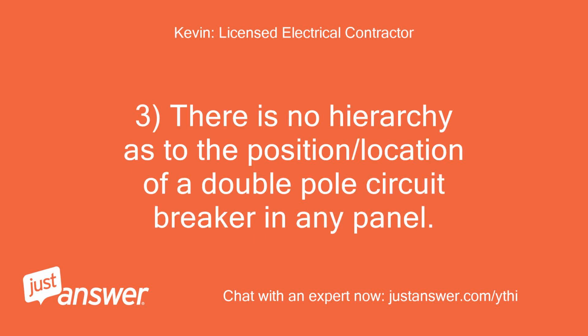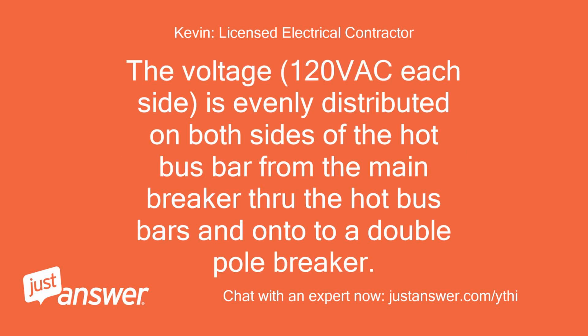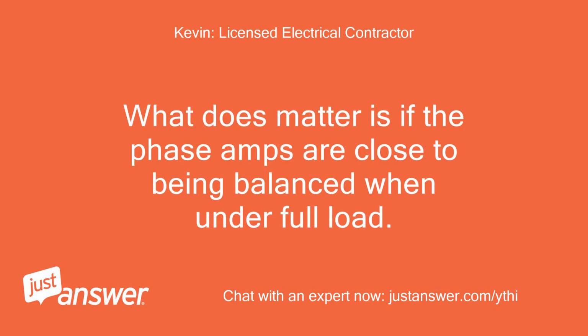3. There is no hierarchy as to the position/location of a double pole circuit breaker in any panel. The voltage, 120 VAC each side, is evenly distributed on both sides of the hot bus bar from the main breaker through the hot bus bars and onto a double pole breaker. What does matter is if the phase amps are close to being balanced when under full load.